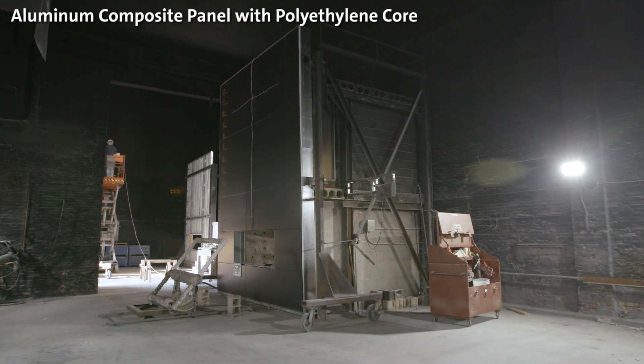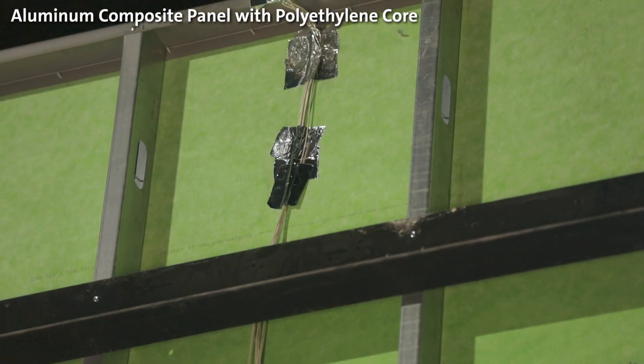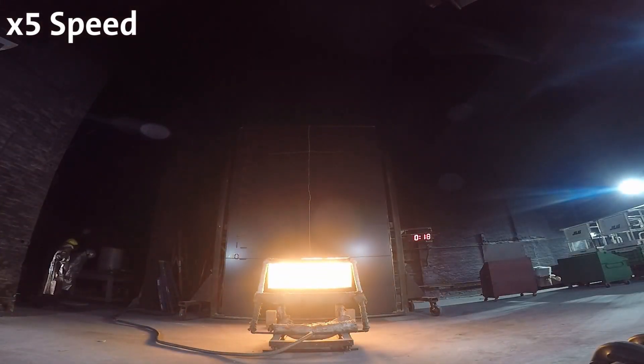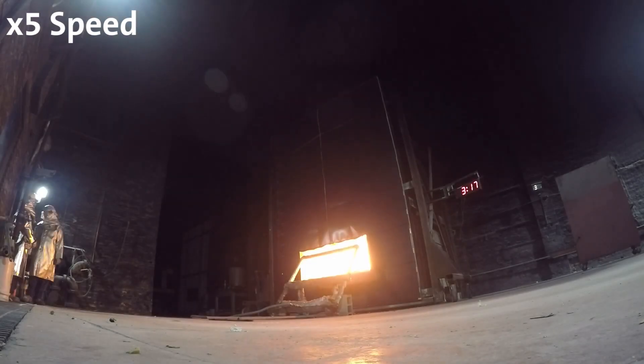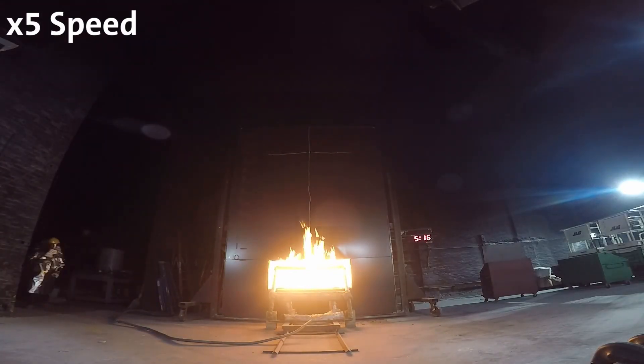The first test assembly is a full wall assembly from inside to outside: interior gypsum board, steel studs with an open cavity and no insulation, exterior sheathing covered by a weather barrier, a three-inch air space, and then the exterior veneer — the ACM. At ignition, most of the flaming is limited to the first floor room. At roughly three minutes and fifteen seconds, burning is visible at the window sill, likely attributed to combustible off-gassing. At five minutes, flaming begins to come out of the window opening and we ignite the window burner.